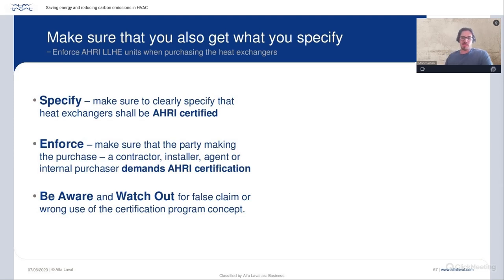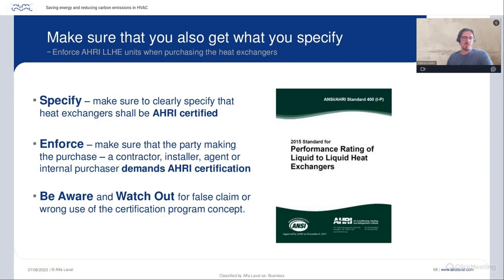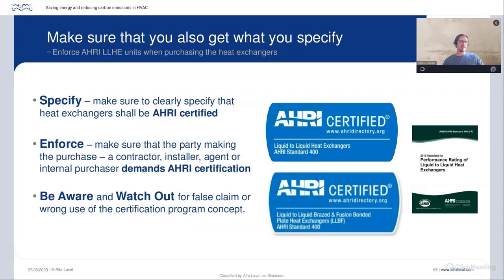And then a small warning is that there are some people in the industry that actually try to fool people. AHRI, it all started with a rating standard. It's a small Bible, which is called AHRI Standard 400. This is a text that describes the testing procedure, how to test and rate the performance of a heat exchanger. And sometimes suppliers would actually claim to be AHRI certified by making references to Standard 400, saying that yes, our units are designed in accordance with the tolerances of this program, but then they are still not included in the certification program. So the unit would not be included in the yearly testing and all the functionalities that are included in the certification program. So you should always be very accurate, saying the unit should be in the certification program, not making a false claim that you are designed according to the tolerances of the rating standard, because that gives you basically zero value.